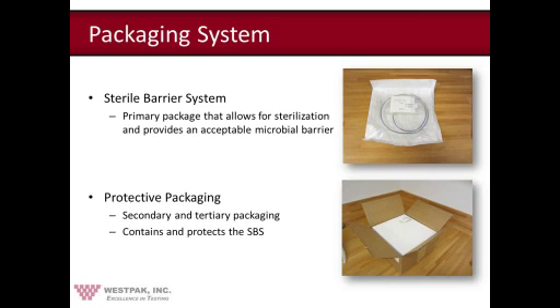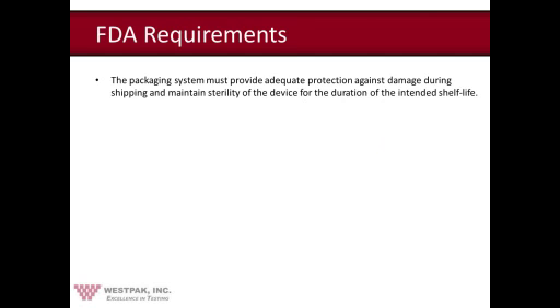So that's what we're going to be focused on, the entire packaging system, and it's that entire package system that must be validated for clearance by the FDA. So I'm going to briefly go over what the FDA is looking for when we're validating this. So obviously validation is one of your critical steps when it comes to getting your product to the market. And this is going to be based on FDA requirements for 510K submission. So what are they looking for exactly?